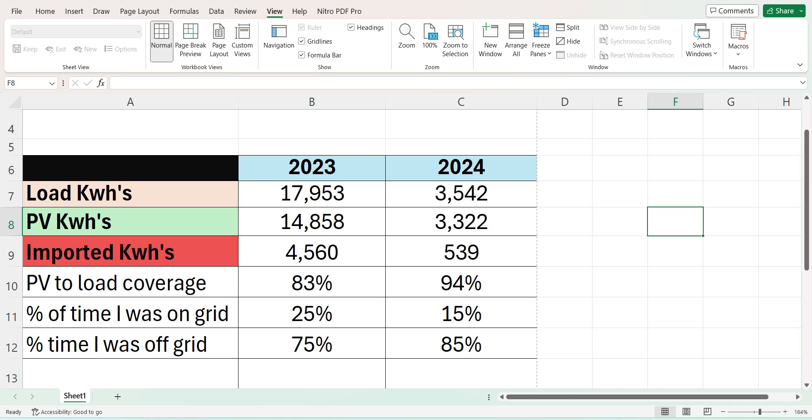So that's how it broke down — I'm off-grid 85% of the time. Because of the two-to-three months I didn't have solar panels running, 2023 was skewed, but it still came out to about what I expected: off-grid about 85% of the time with only 30 kilowatt hours of batteries. If you use less power than me — I average about 60 kilowatt hours per day, and the average home uses about half that — you'd probably be closer to 95% off-grid with only 30 kilowatt hours of storage.